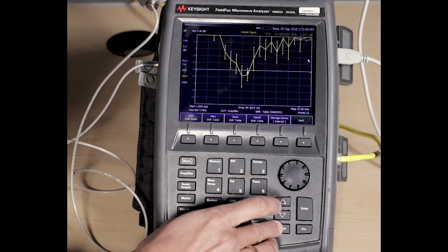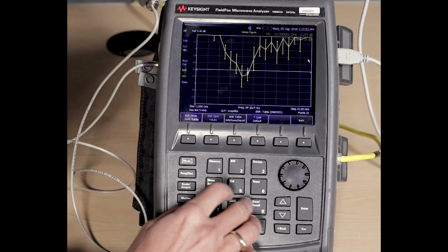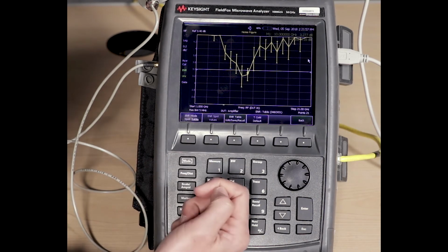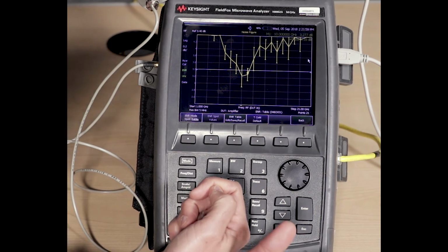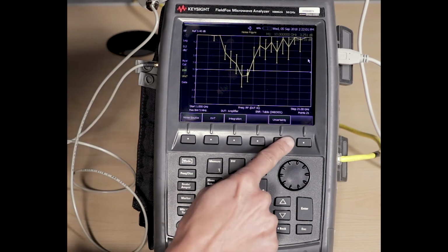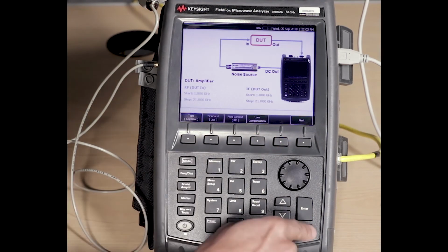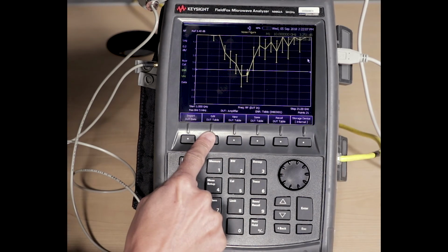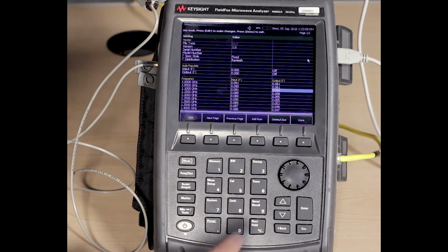We did this to prevent people from thinking they're applying the mismatch uncertainty, but not actually calculating it. It's really easy to not have the right values in this table and have a false sense of correction.